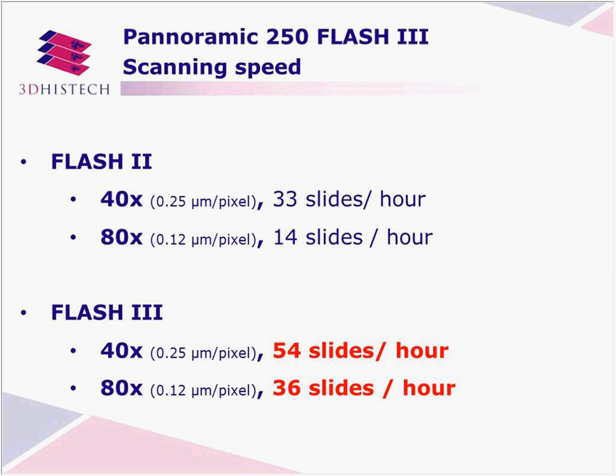In the new system, the higher resolution will also be available with the objective changer, and you see an even higher speed increase. The previous system was capable of scanning 14 slides per hour, and now we will be able to scan 36 slides per hour. The speed increase is larger with the other objective because with the smaller field of view, with the same stage movement speed, we can grab more fields of view, and the stronger PC can also process them, and that's why we have a higher increase at the higher resolution.